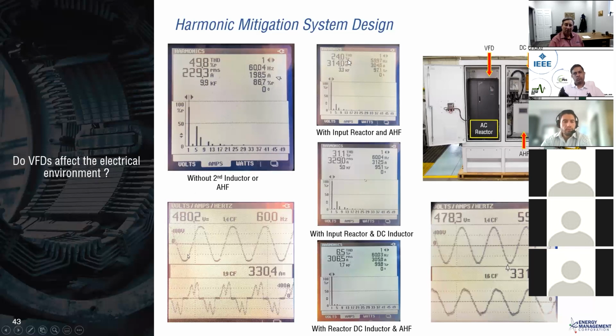We were only getting the harmonics down to 24%, only dropping them about half, which makes sense because we had so much to start with. So we added another DC inductor, which, without the filter running, brought us from 49% to 31%. That made a huge difference in our filter performing where we expected it to, with an outcome of 6.5% current THD and this waveform, which is very acceptable.